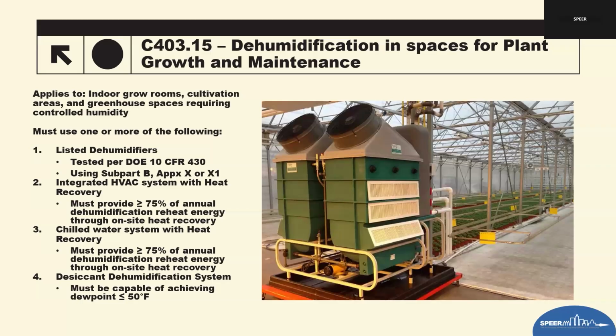Option number three, chilled water system with heat recovery. Likewise, a chilled water system may be used provided they incorporate on-site heat recovery that also fulfills 75% or more of the annual dehumidification reheat needs. Both integrated HVAC systems and chilled water systems achieve the same goal, reducing energy consumption by recycling internal wasted heat. Option four, desiccant dehumidification. A solid or liquid desiccant system may be used if the space design requires a dew point no higher than 50°F.